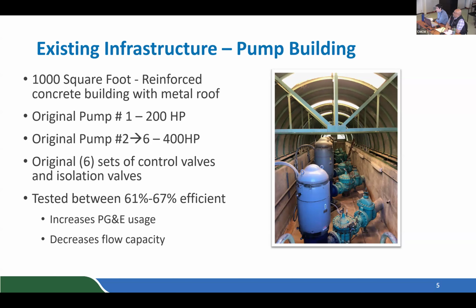During this 2-year process, we did do a full condition assessment of the pump station, and these pumps tested between 61 and 67% efficient, which is considered poor. Anything under 70% efficient is in the replace or rebuild range. Just for your knowledge, when you buy a brand new pump, you're around 85, 86% efficient. And because of these inefficiencies, it increases the district's PG&E power usage and also decreases the flow capacity.